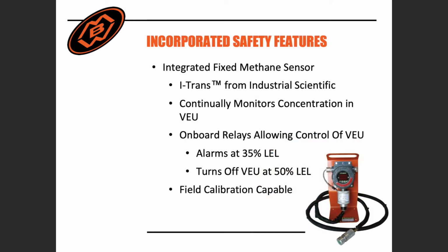MBW has incorporated a methane LEL sensor that monitors in real time the gas concentration going through the machine, which helps provide a safe environment for crew members. If the LEL goes over 35% LEL, an audible alarm will sound, and if the LEL level exceeds 50 LEL, the unit will shut off. The operator is given full control of the VEU through an air bypass valve that can adjust to ensure the LEL levels are safe. This sensor does need to be calibrated quarterly, just like any other gas detecting instruments.